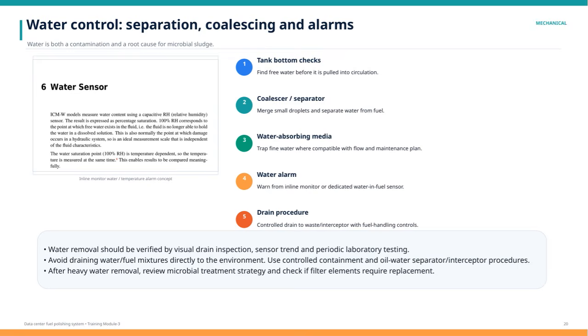Additionally, water-absorbing media play an important role. These materials trap fine water droplets where compatible with the system's flow and maintenance requirements, capturing water that might otherwise pass through. Water alarms are another key component. These alarms can be triggered by inline monitors or dedicated water-in-fuel sensors, providing early warnings so corrective action can be taken before problems escalate. Finally, a controlled drain procedure is necessary for safely removing water. This involves draining water to a waste or interceptor system with fuel handling controls to avoid environmental contamination.